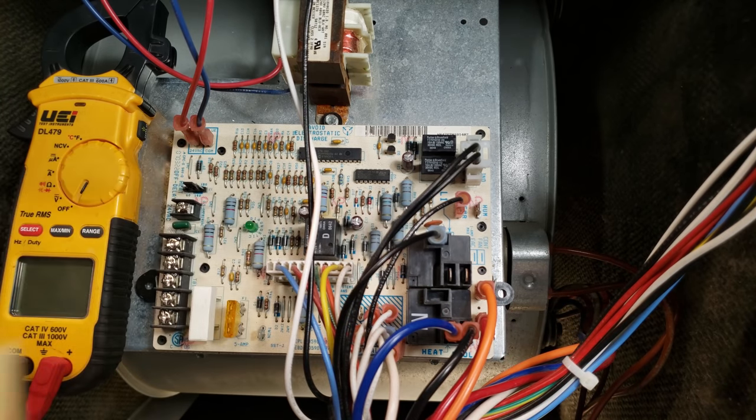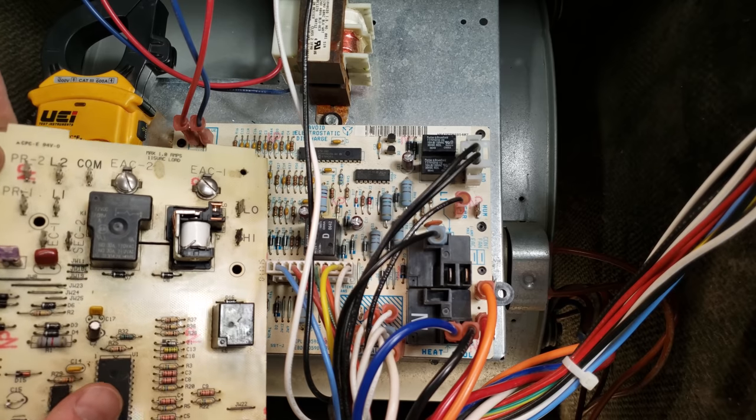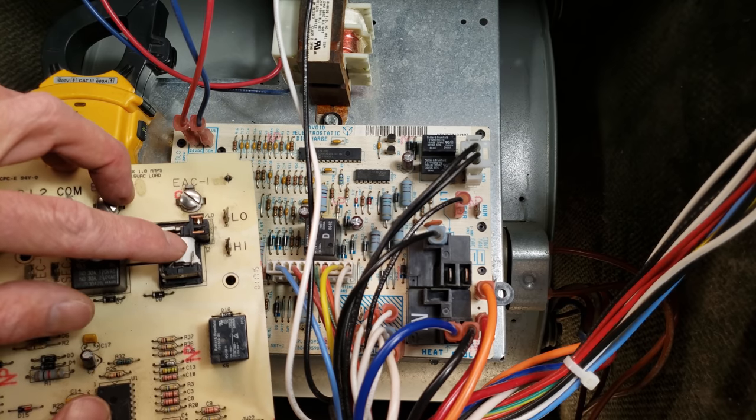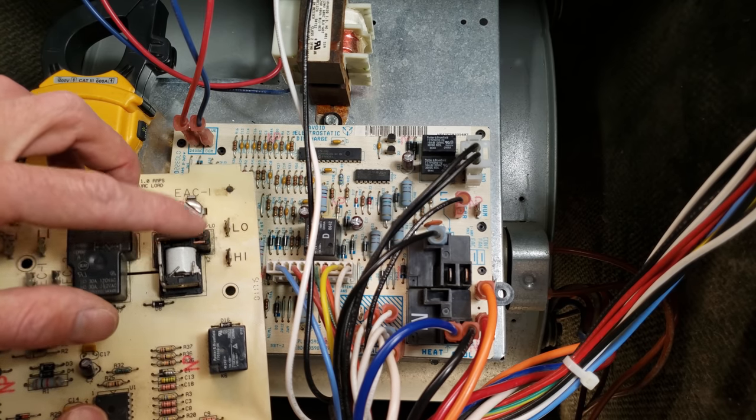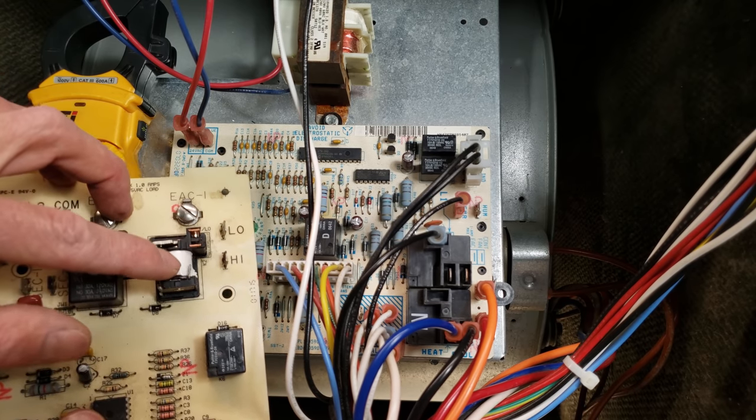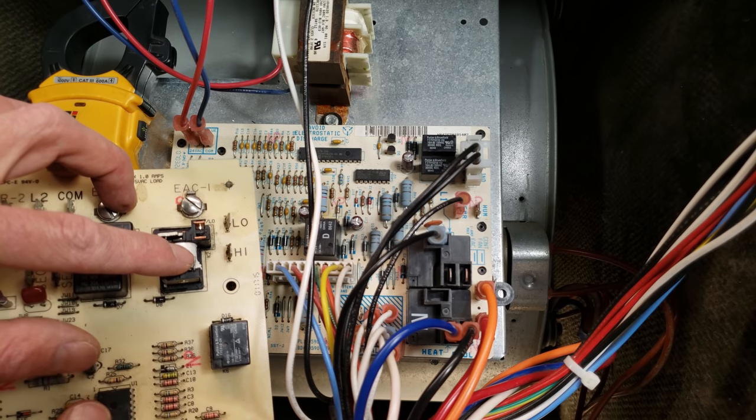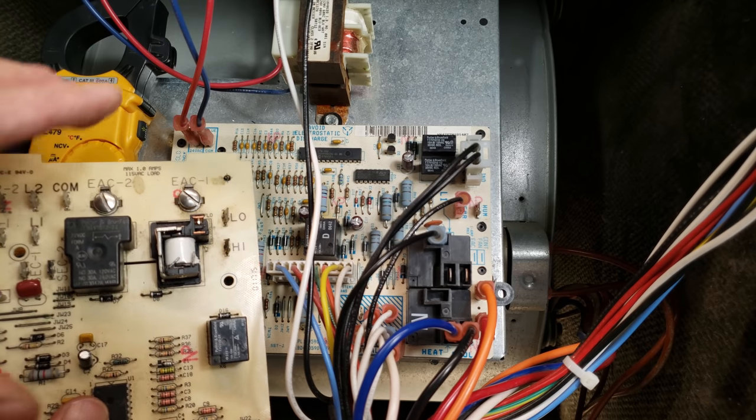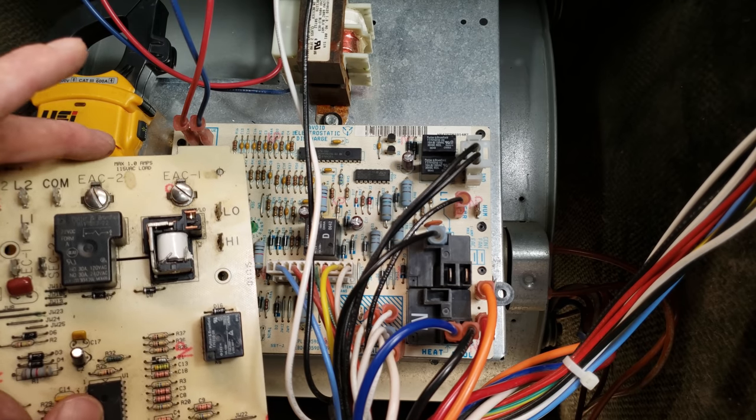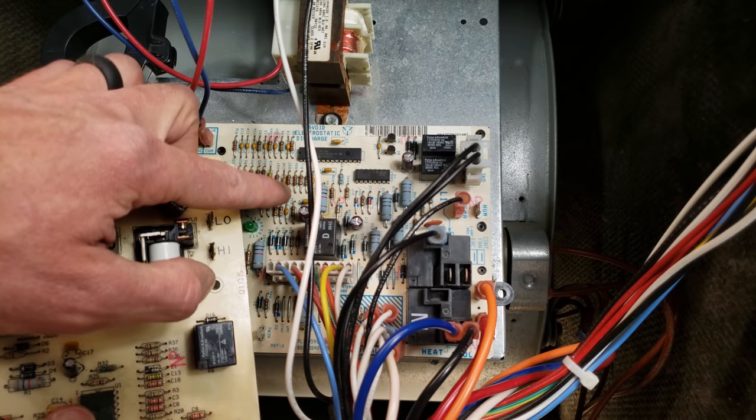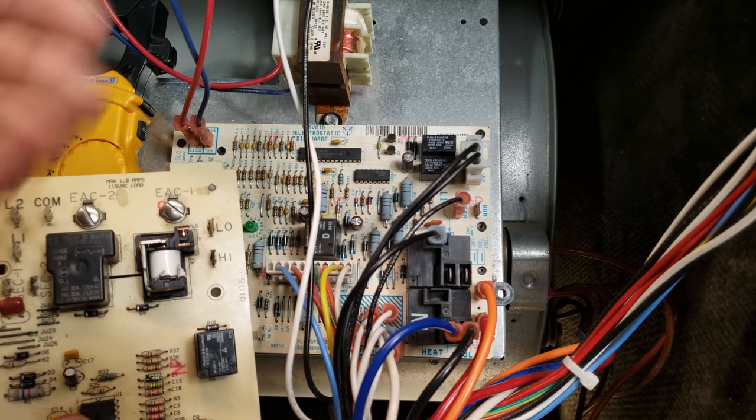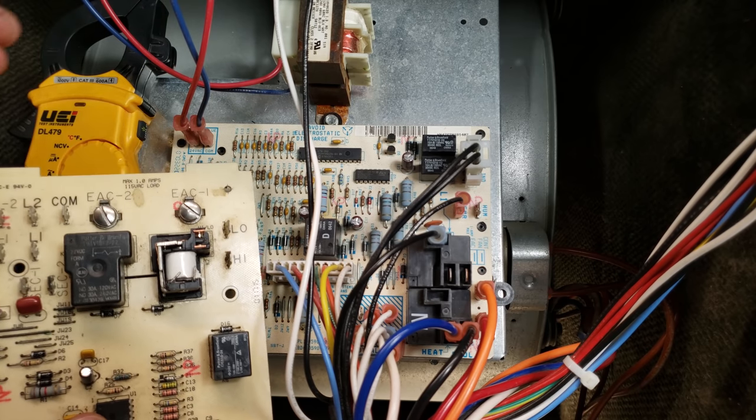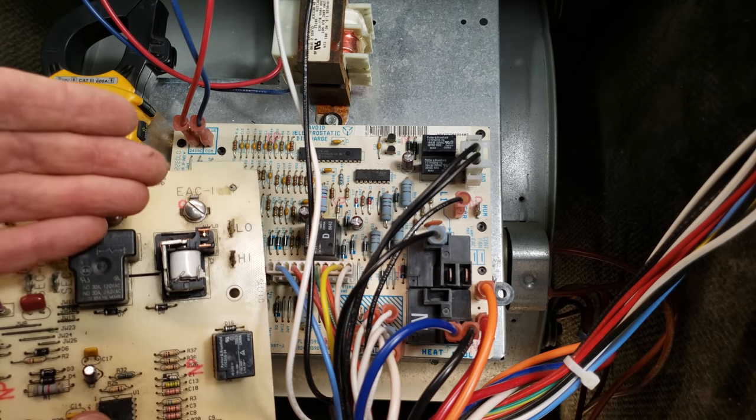Underneath these black boxes you have a relay, made up of a coil and your contacts. This is a direct current relay. On the control board, regardless of whether it's an old one like this or a newer one, it's going to rectify the voltage from alternating current to direct current.